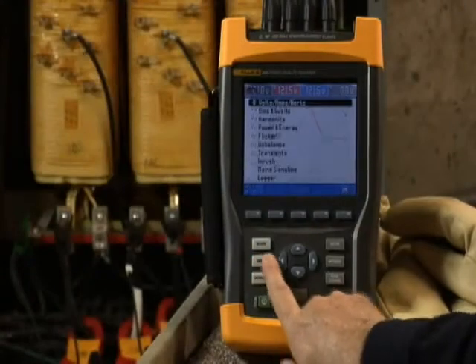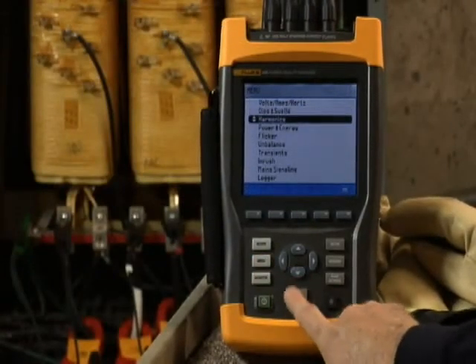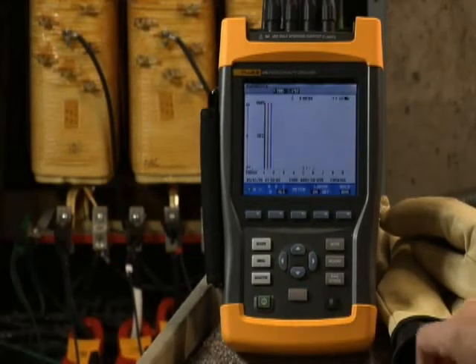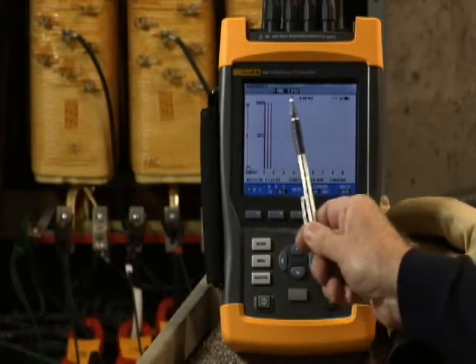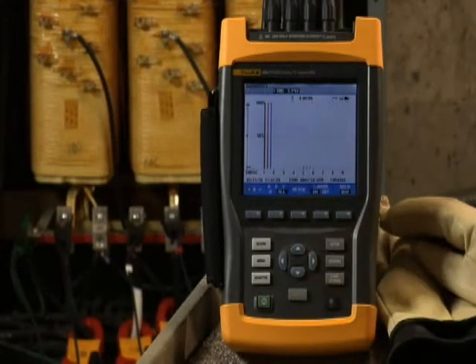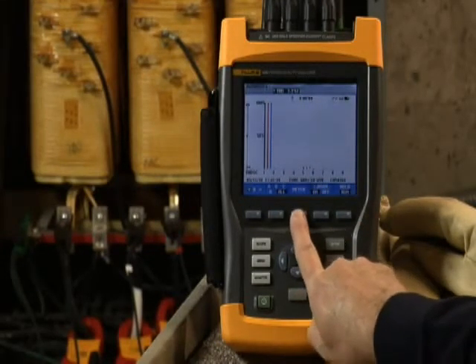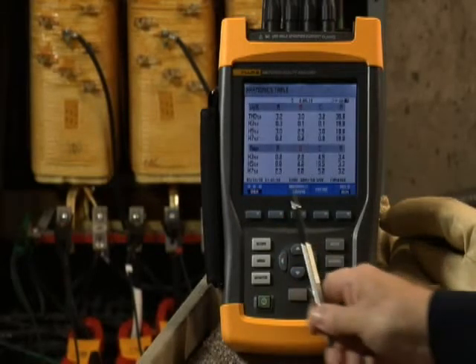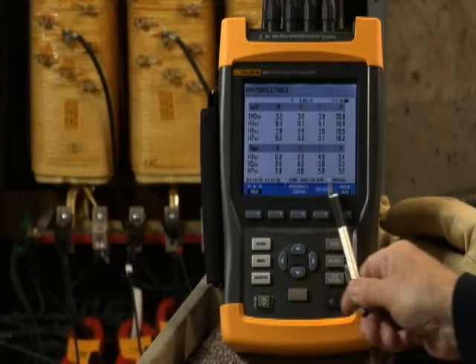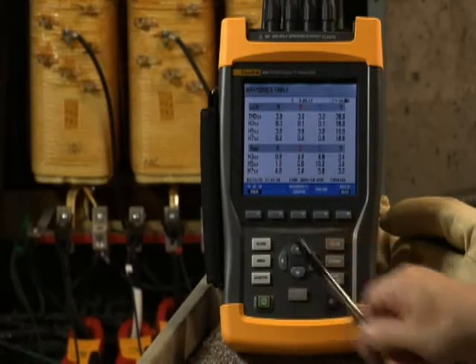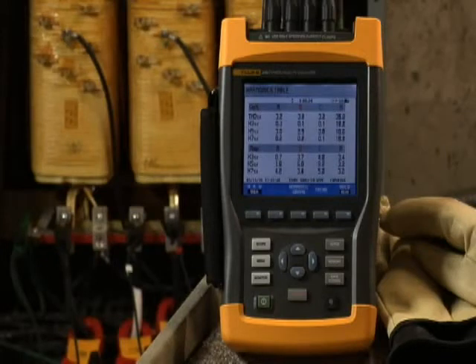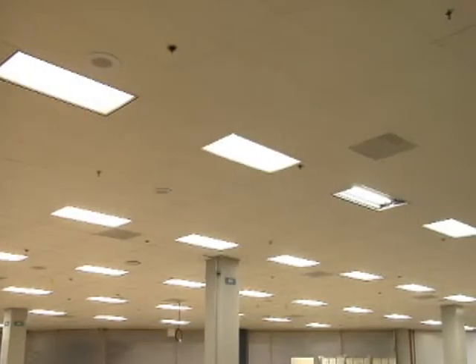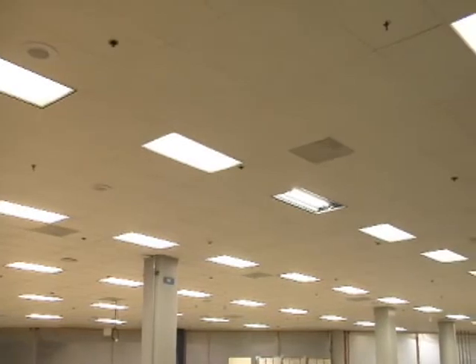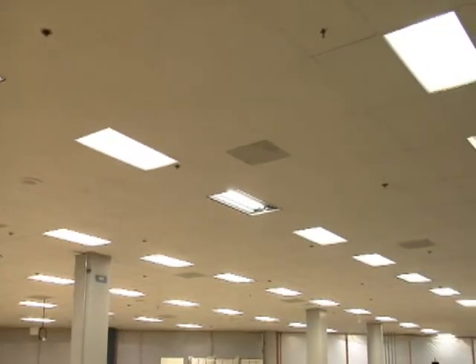Back to our transformer. If the voltage and current are reasonably balanced, then check the harmonics screen. Is total harmonic distortion, or THD for voltage, at less than 5%? If it is higher, dig into the individual spectrums, the 3rd, 5th, and 7th harmonic, and determine the source of the harmonics. Excessive harmonics on the third or fifth level often point to interference from electronic loads. If you do find evidence of harmonics, move downstream from the transformer to the individual loads. Look for things like high-efficiency lighting systems. When you find the root cause, you'll probably need to install a filter.